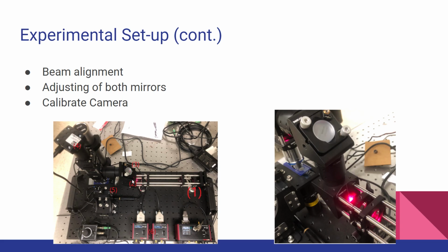The first mirror is then adjusted with the top mirror removed here so that the beam is shining straight up, so that the beam is coming straight out of the top, and then the second mirror is then replaced and the beam is shined over into the vertical section. In the vertical section, a screw cap is removed over here on the left of it, so you can see into the third mirror and lens portion, and the adjustment screws on the second mirror are used so that the beam shines directly down onto the sample.